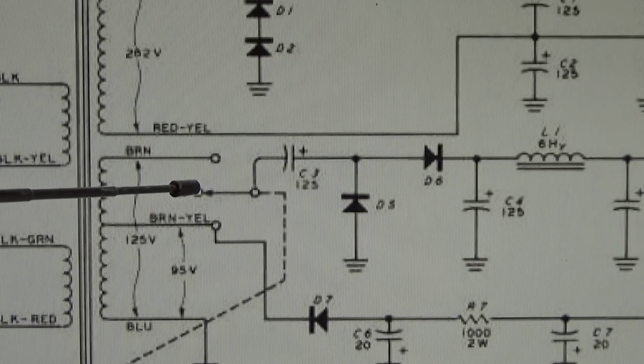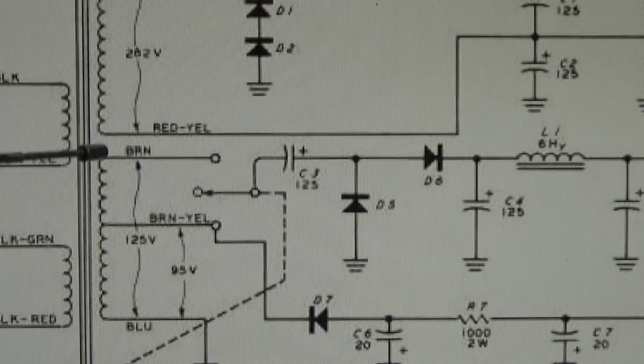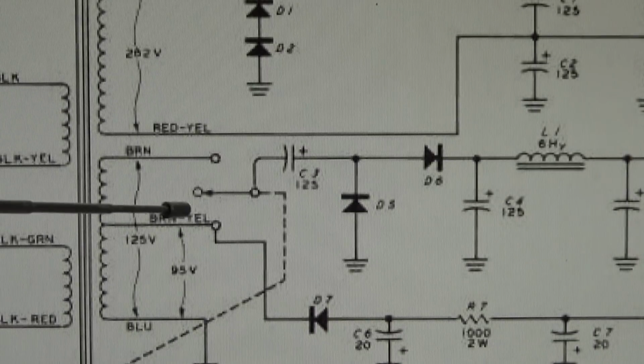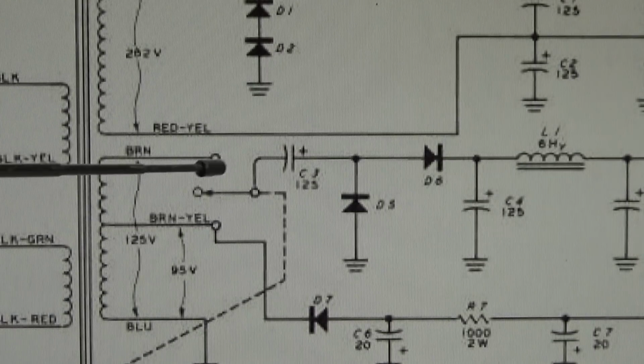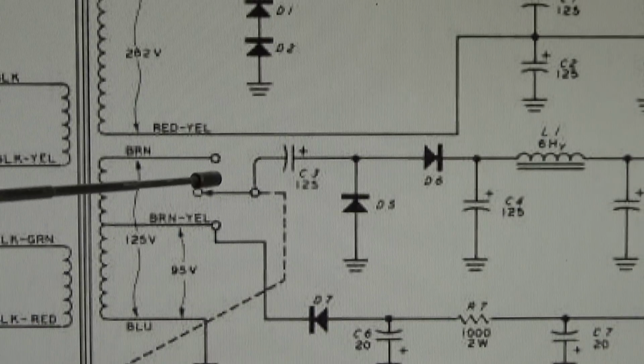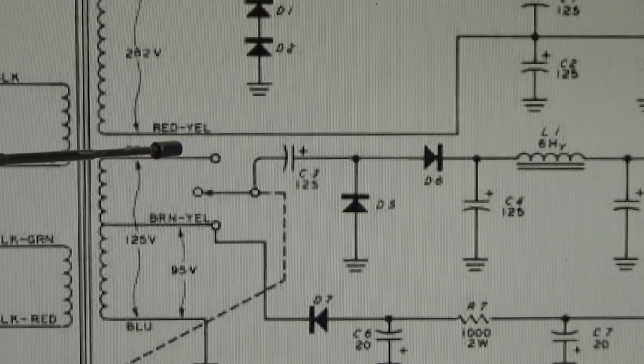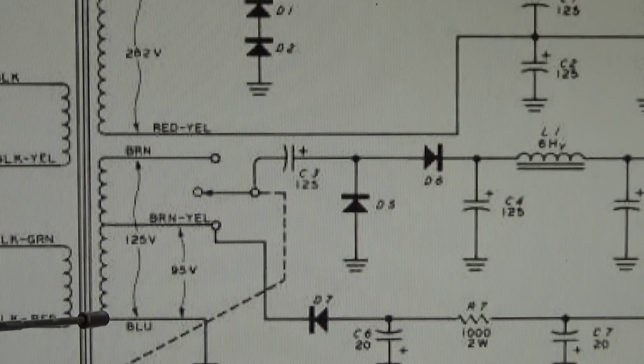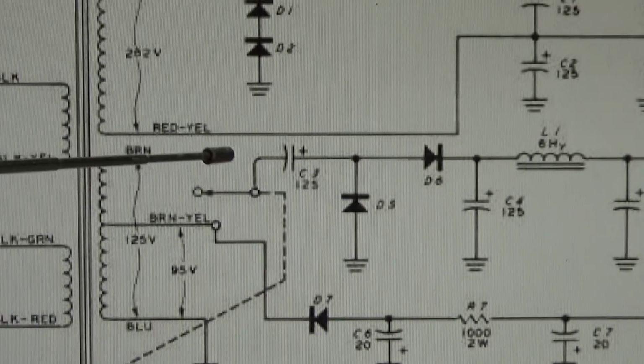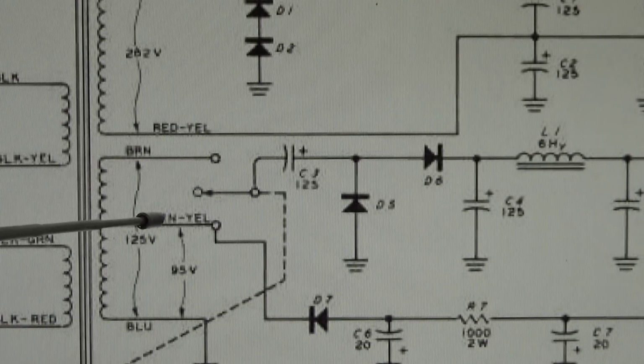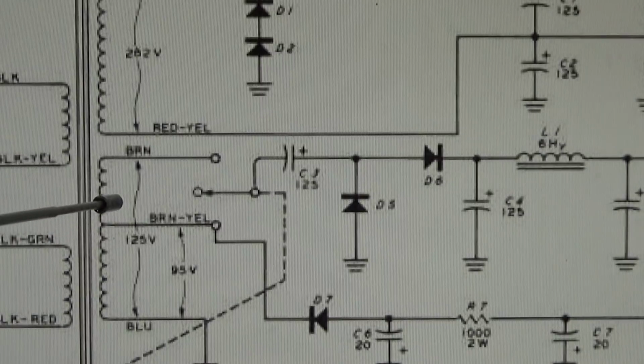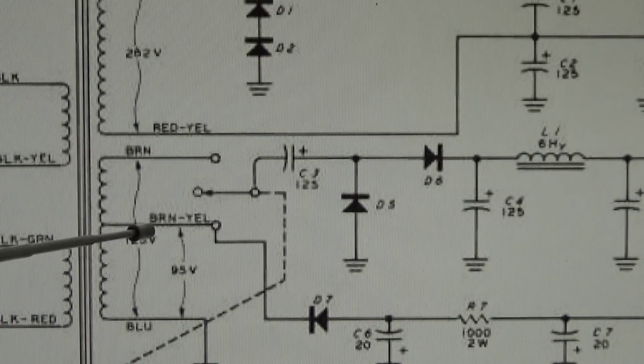So in the middle, of course, it's switched off. If we switch it to the brown-yellow portion of our transformer, we get 125. When we switch up to the brown wire, we're using the whole coil, and we expect 300 volts. That's not working simply because it's wrongly wired at our toggle switch.